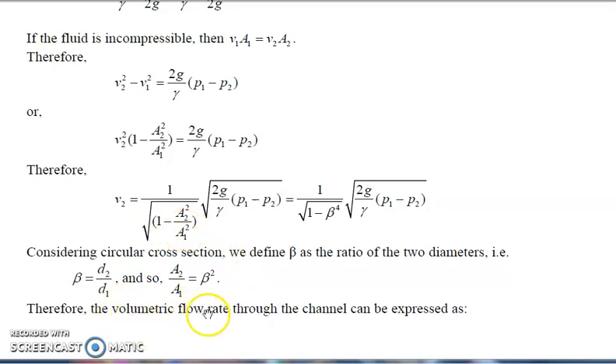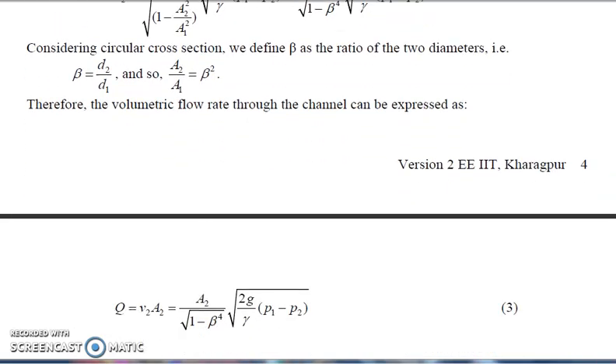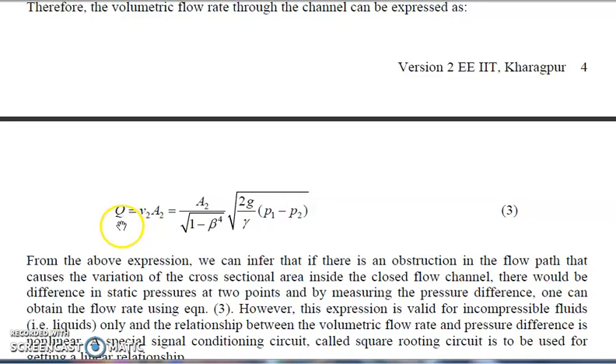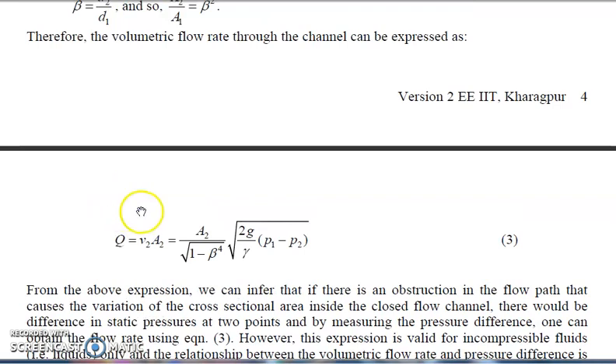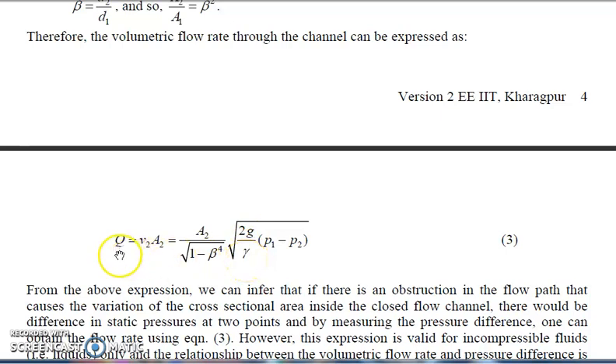The volumetric flow rate Q = V2 · A2. Substituting the values obtained using beta, this complete formula gives the volumetric flow rate. Note that area A2 is constant, beta is constant, g is constant, and gamma is constant. Therefore, the volumetric flow rate Q is directly proportional to the square root of the pressure difference (P1 - P2). This shows how we can measure flow by measuring the pressure difference at two different sections of a pipe.